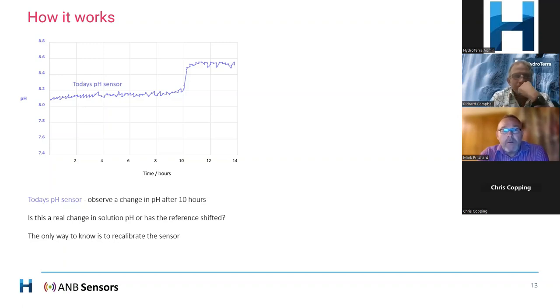Let's have a look at how it works. The slide you can see there shows today's pH sensor, a glass-based pH sensor. That's a true reading of a sensor in a tank. You see after 10 hours there is drift on the pH. Now, no one really knows, is that drift or is it a change in the pH level? The only way you're going to know that is to recalibrate the sensor.